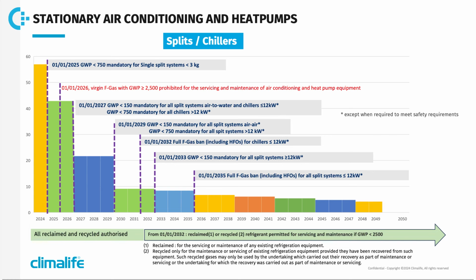From January 1st, 2027, it will be mandatory to use refrigerant with a GWP less than 150 for all splits and for chillers up to 12 kilowatt. And refrigerants with a GWP of less than 750 for chillers of more than 12 kilowatt. And always except for safety requirements. The next stage will take place on January 1st, 2029, when all air-to-air splits will be required to use refrigerant with a GWP of less than 150, and splits of more than 12 kilowatt will be required to use refrigerant with a GWP of less than 750, but still exempt if there are safety requirements.